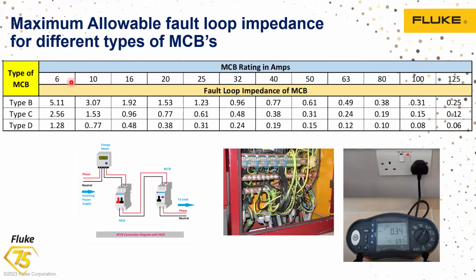So similarly, we have MCBs at different ratings. For example, in most cases we could see 32 ampere MCB ratings. If it is type B, then it is 0.96, and if it is type C, it is 0.48, and if it is type D, it will be close to 0.24. So you can see the values here, showing how much fault loop impedance will be available in these kinds of conditions.